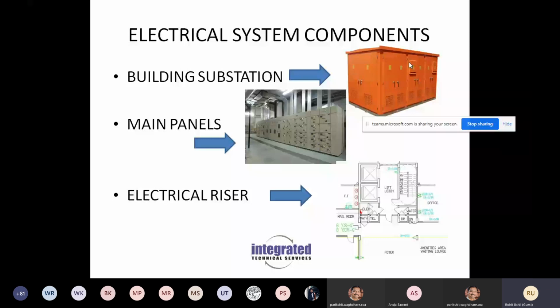Now, through these transmission lines, they come to area receiving stations, and from the receiving stations, it comes to something called a building substation. Now, at the building substation, the voltage, which is the transmission voltage, is usually in kilovolts, like 132 or 66 or 11 kilovolts. And what we actually use in our built environment is 440 volts. So to step it down from say 11,000 volts to 440 volts, we require something called a substation.